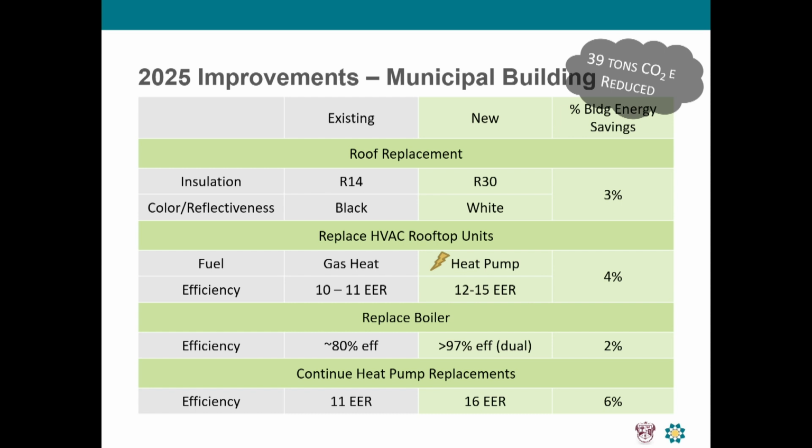Air source heat pumps, again, may lose capacity in the winter. Geothermal heat pumps may even lose capacity in the winter as the loop temperature starts to drop. Having that boiler on the loop makes sure that we are consistent throughout the year and can maintain the heat pumps, which are doing the majority of your heating and cooling, at their peak efficiency. So when you factor all those numbers in together, we end up with a more efficient overall system.